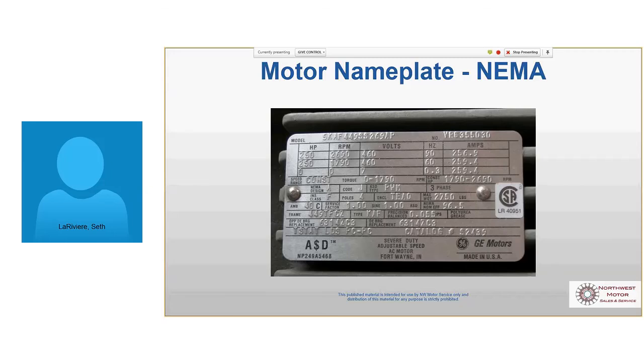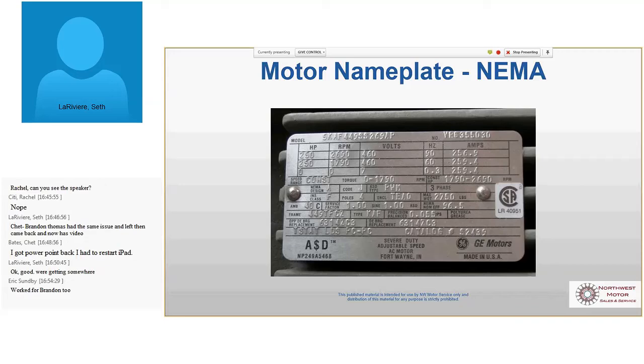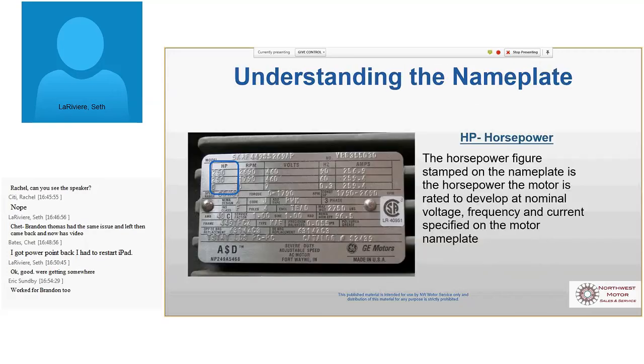It tells you it gets constant torque from 0 speed to 1800, constant horsepower from base speed to 2700. It gives you a lot of different information: PWM type drive, the weight of the motor, a lot of good information on there. A normal motor that's not an adjustable frequency drive motor won't have that additional line. It would just have the 1800 RPM, because it's not designed to be operated above base speed. So that horsepower number is what the motor is designed to develop.